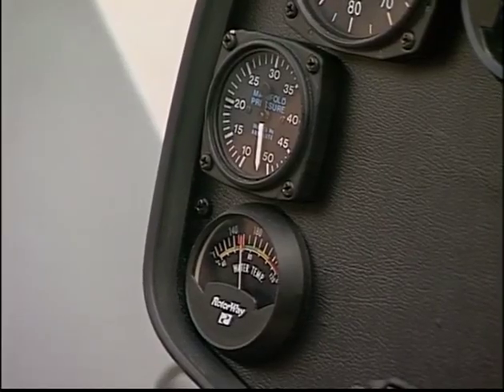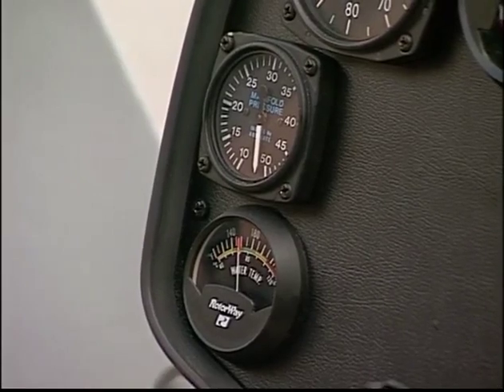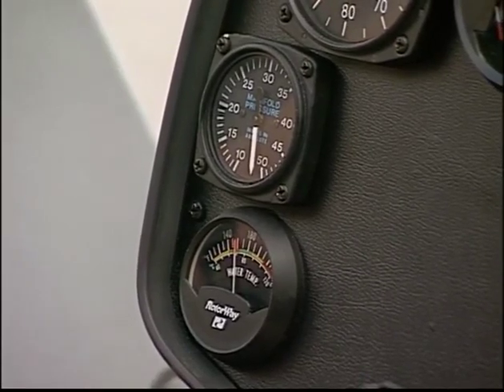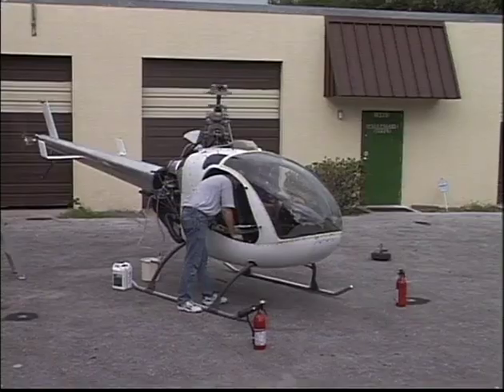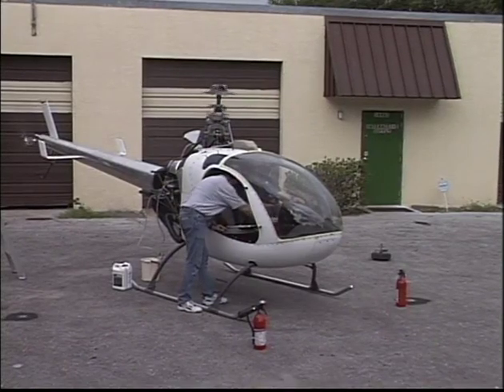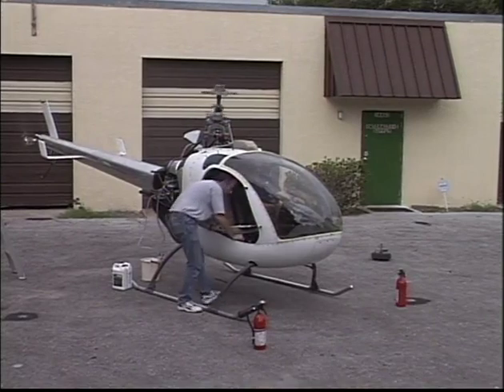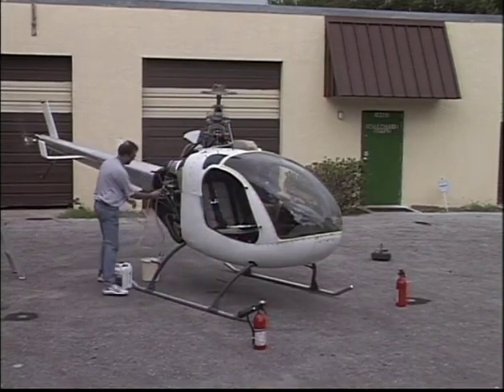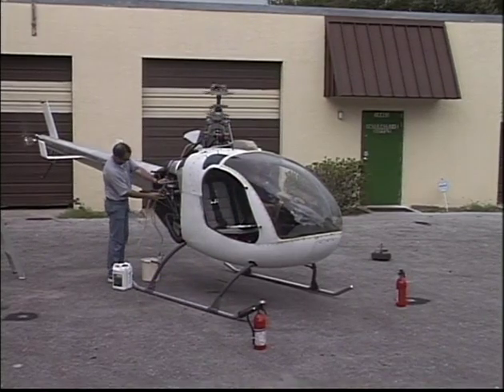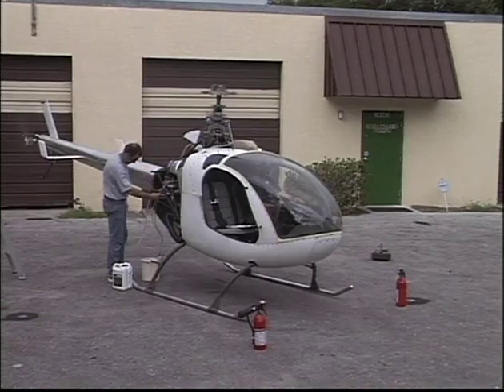Caution: do not allow the water temperature to exceed 185 degrees Fahrenheit during the initial startup period. If a rapid and continuous increase in water temperature occurs and cannot be stopped by bleeding at the water pump, the engine must be stopped before the water temperature reaches 185 degrees Fahrenheit. Allow the engine to cool, then bleed out the air at the 3 air bleed valve locations.